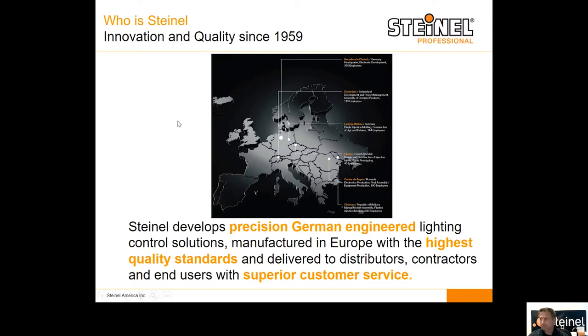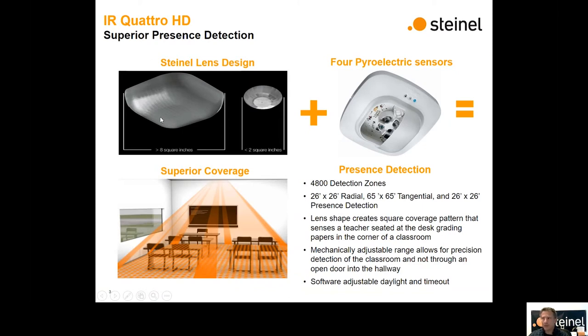So I'll quickly get into an example of our innovative technology, the IR Quattro HD presence detector. It's an infrared sensor, but we've done two things that make it far superior to any other product in the market. Number one, the lens design is a little bigger and square. Square lens gives us square coverage for square rooms. If you think about round sensors, they give you round coverage in a square room, leaving the corners exposed where there's no detection.